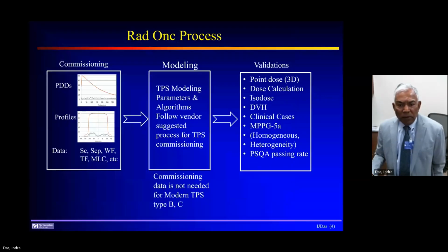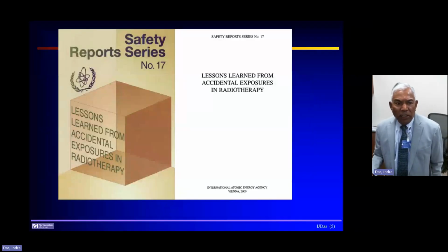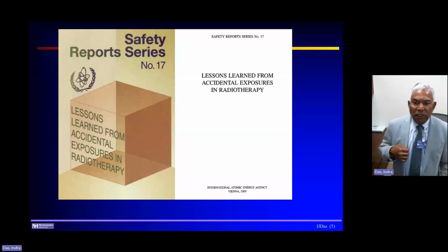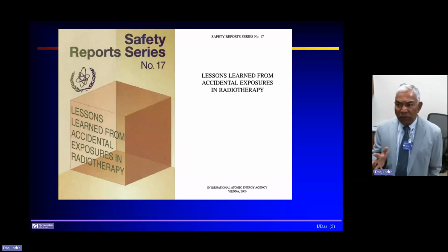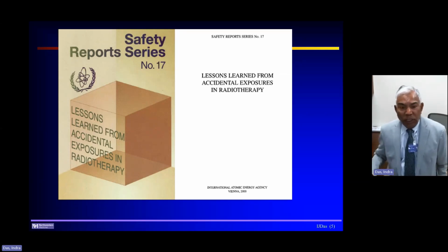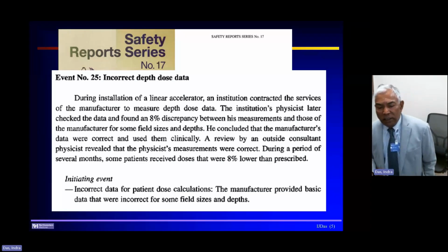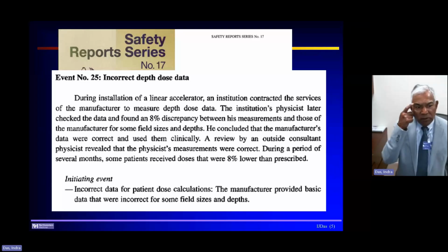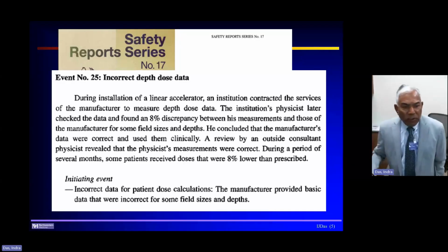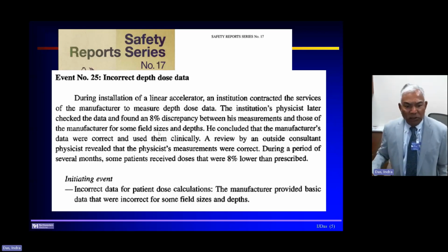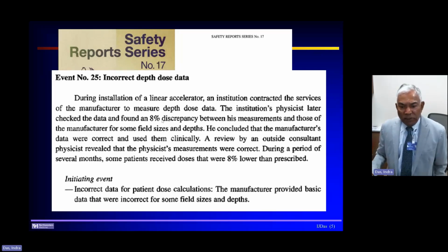Now, we are going to just go back in time. This was the International Atomic Energy Agency. They did some surveys. It's obviously a 24-year-old document. And they provided information on what the problems are and where they found the errors. In this particular document, they found a lot of scenarios, and I'm just going to give you some specific events. During the installation of linear accelerators, the physicist found that there was an 8% discrepancy between his measurement and the one the manufacturer quoted. So 8%, the physicist found.